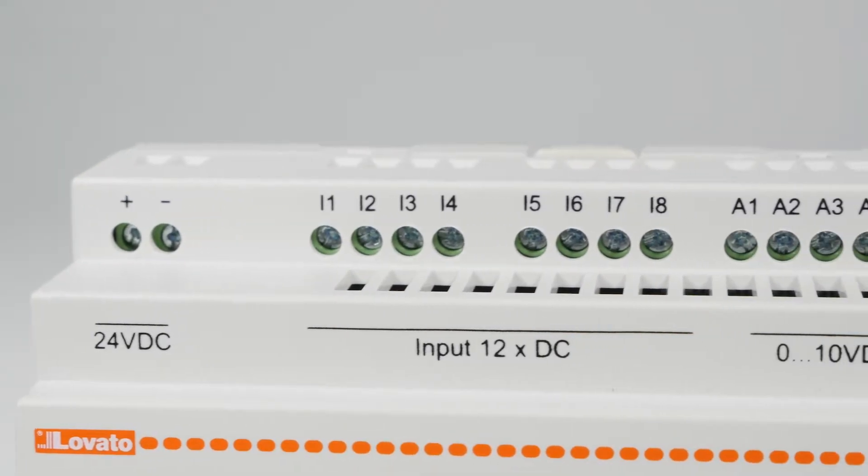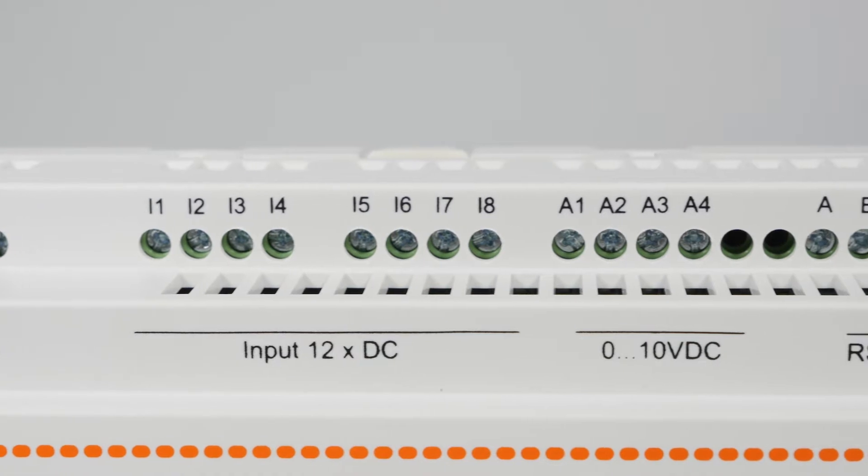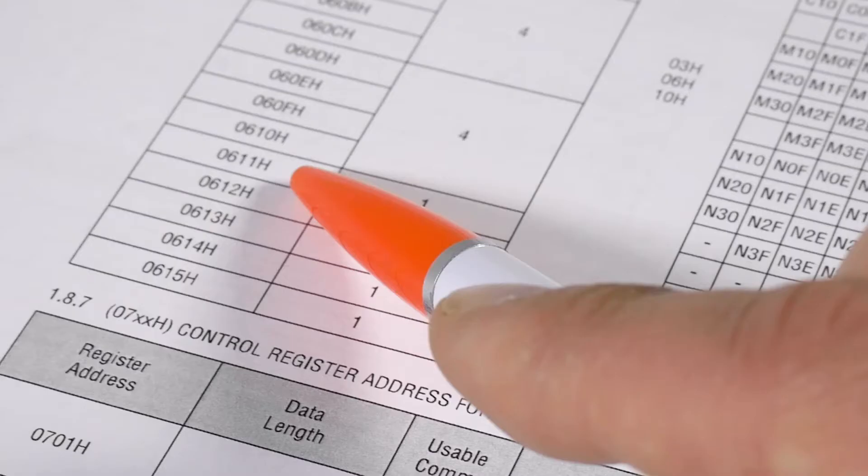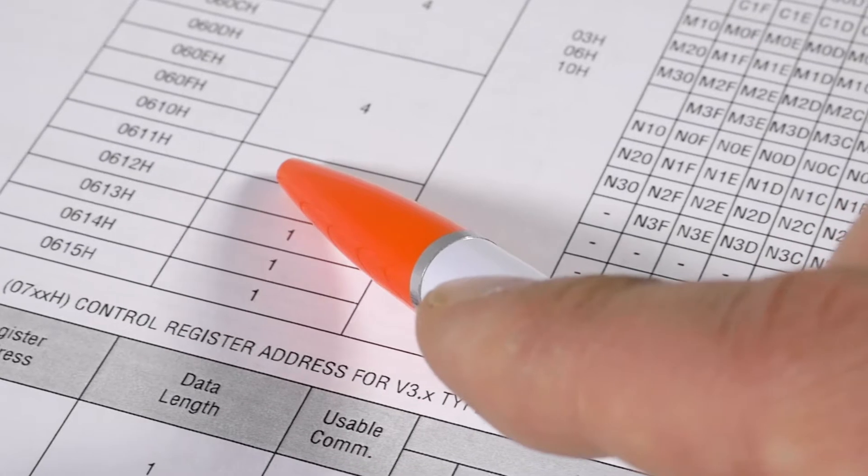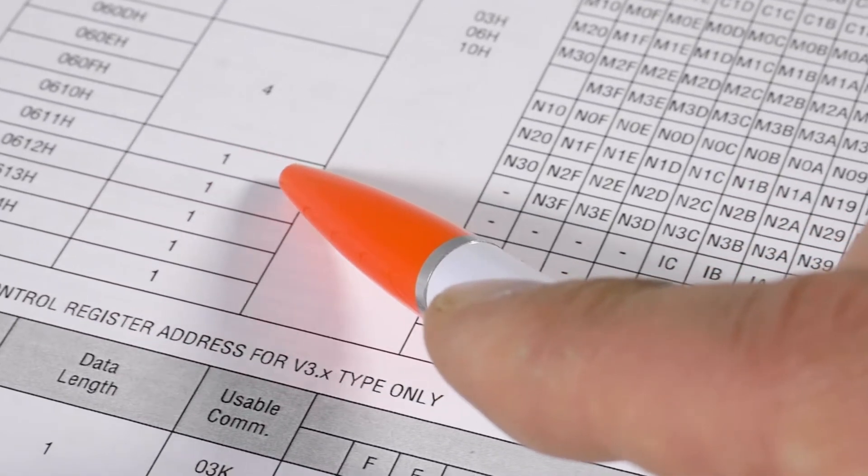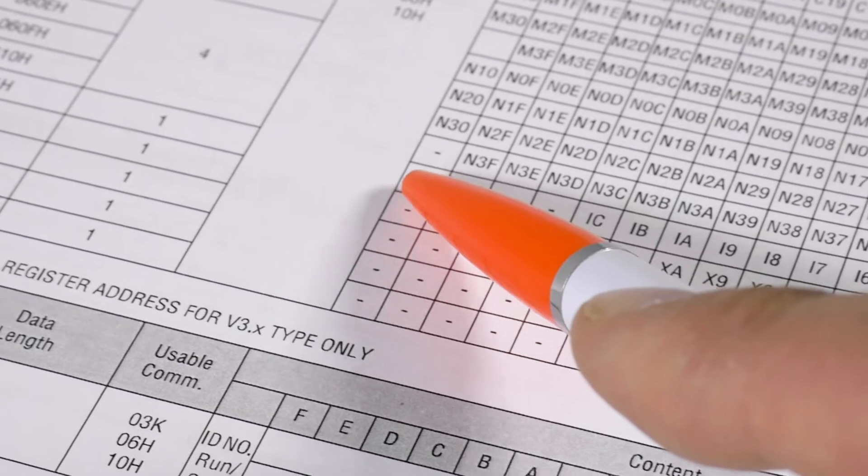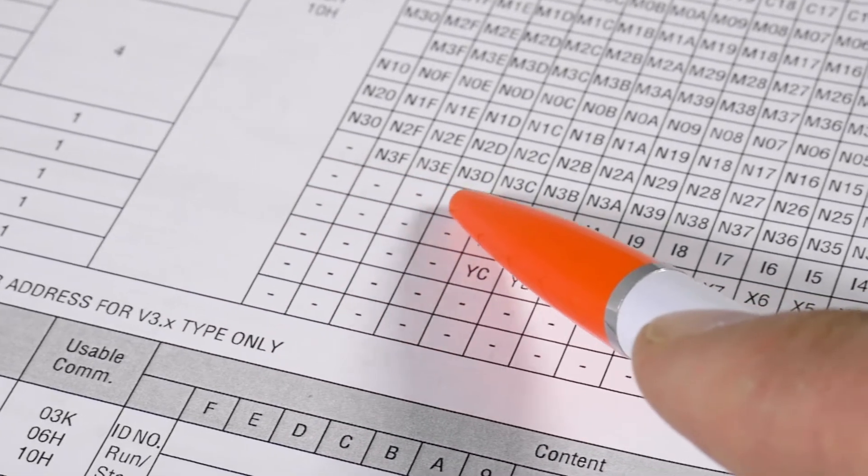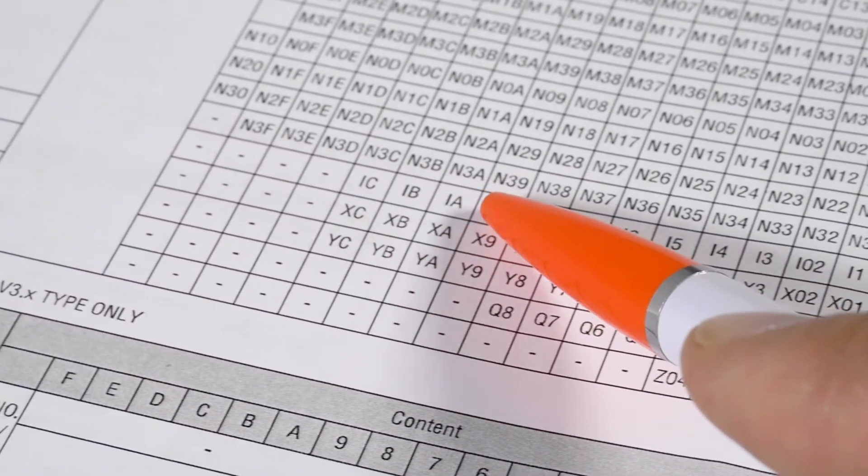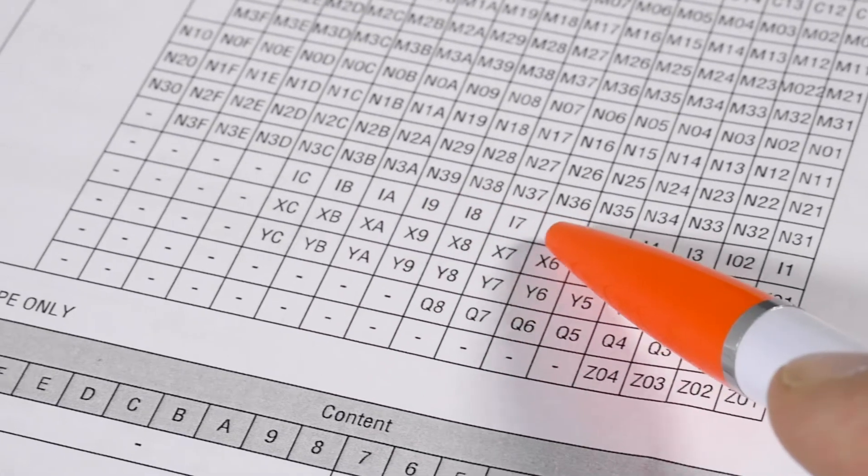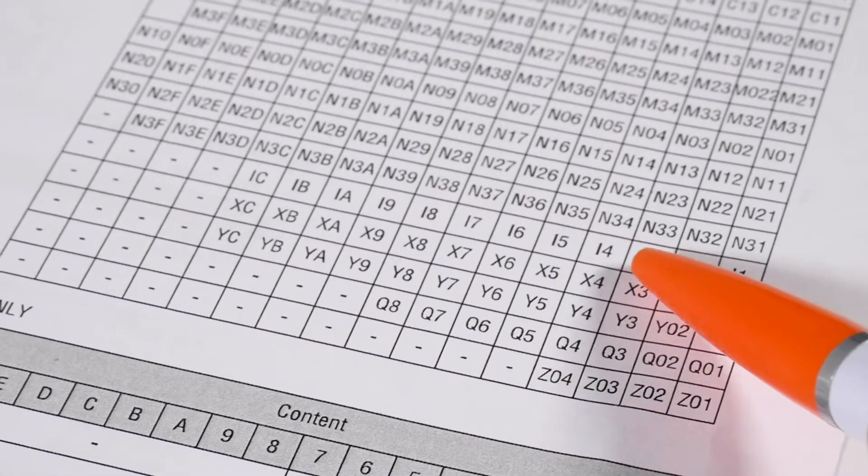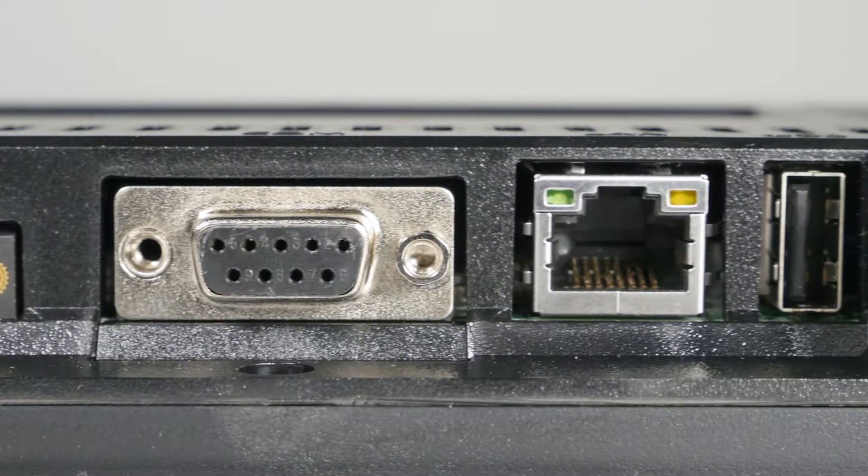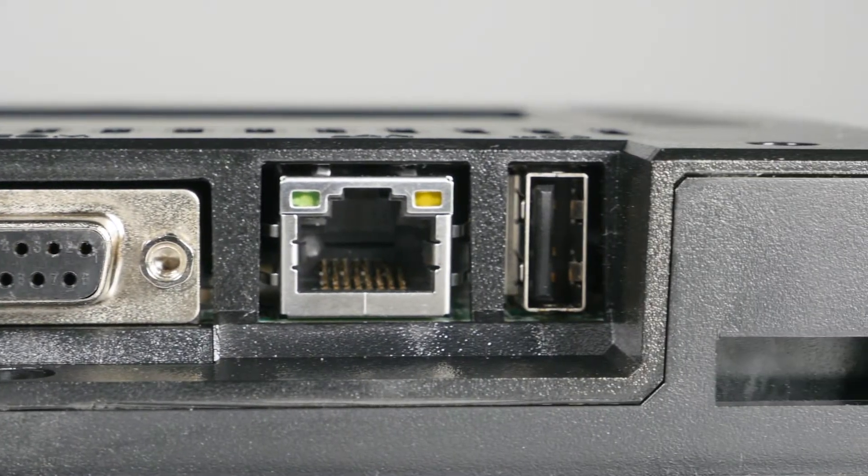Use the Modbus manual of the LRD series micro PLC to consult the corresponding register, mapped to the address 611 hexadecimal, which is 1553 in decimal. It is one word long and contains the states of all the digital inputs integrated in the micro PLC, from I1 to IC. This means you can read them all at once, without having to configure them individually.